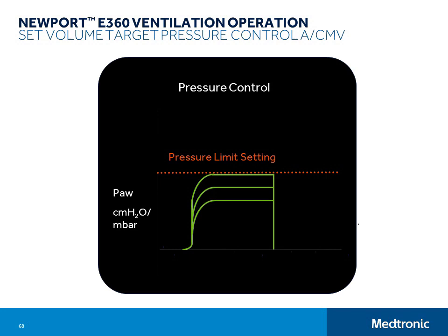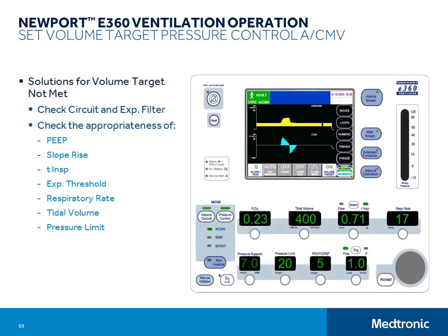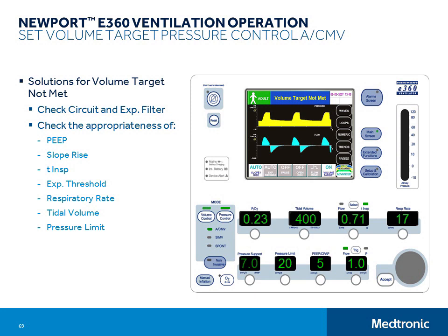When using the VTPC breath type, there is an additional alarm. It is called the volume target not met alarm. If this alarm occurs, it means that your settings will not allow the ventilator to deliver the set tidal volume within the pressure limit you have set. Your first response to this alarm should be to ensure that the circuit and expiratory filter are not imposing expiratory resistance. Then take all necessary steps to improve volume delivery by adjusting the PEEP, slope rise, inspiratory time, expiratory threshold, and respiratory rate levels. If none of those adjustments resolve the alarm violation, you may need to increase the amount of pressure change you allow for the volume to be delivered or decrease the tidal volume setting to resolve it.